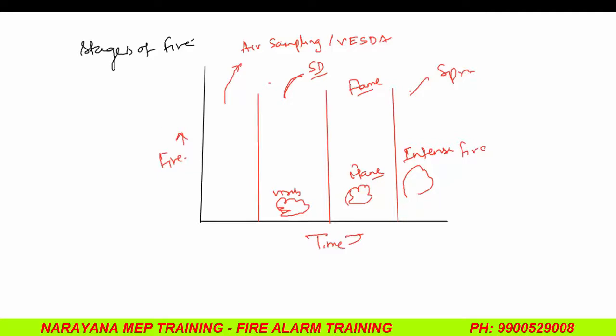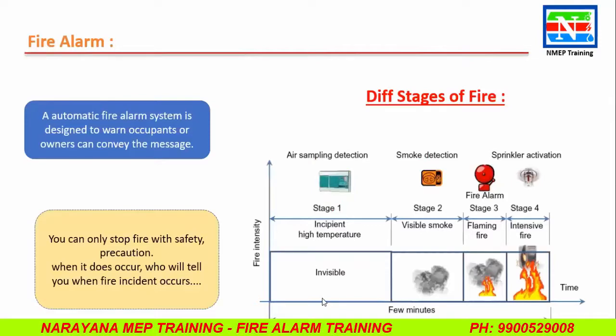So, here you can see the different stages of fire as we discussed — fire intensity with respect to time. In the invisible stage, we have air sampling detectors, or VESDA. Second is visible smoke, which will be caught by your smoke detector. Third is flame. Stage four is intense fire — you have the sprinkler activation system. Basically, fire alarm is designed to warn the occupants, or to convey to the owner that fire has happened.